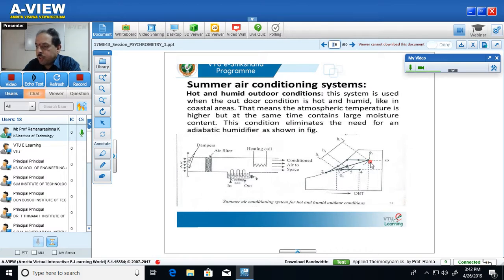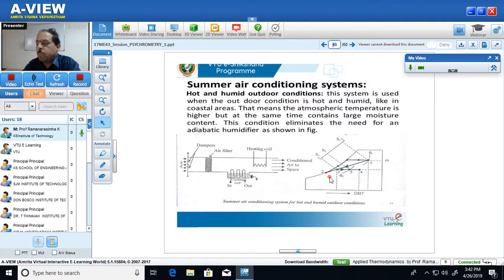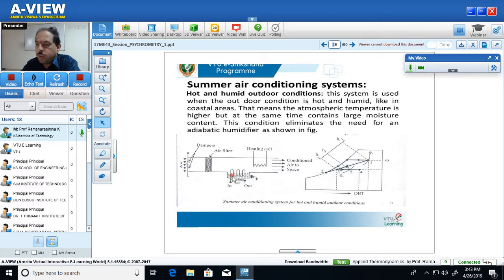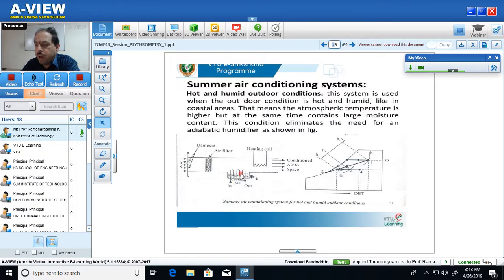Consider the process 1 to 2 as a whole. During process 1 to 2, temperature decreases from Td1 to Td2, and specific humidity also decreases from W1 to W2. So when hot and humid air passes through the cooling coil, two things happen: the air rejects heat to the cooling medium so temperature decreases, and excess water vapors are removed — the dehumidification process — so specific humidity also decreases.